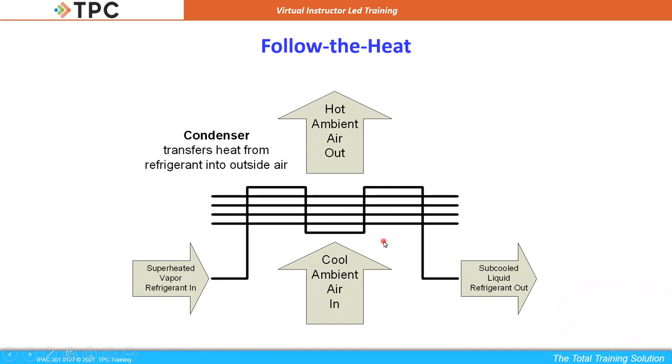So as I was saying, as far as location, if you are in Arizona, you're going to have to run your condenser temperature a little higher than what you would in Pennsylvania. Right now, it's only 80 degrees out. So if we get to 95 saturation temperature, that's cool enough that it's going to pull heat out of the refrigerant and cause the refrigerant to change back into a liquid.